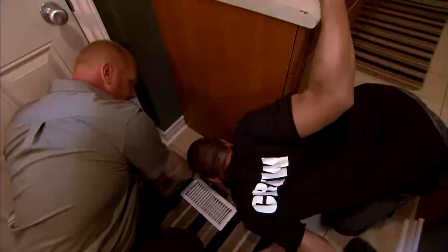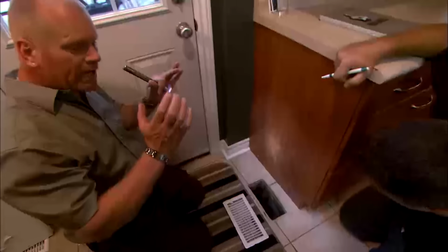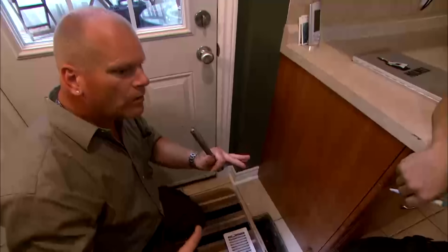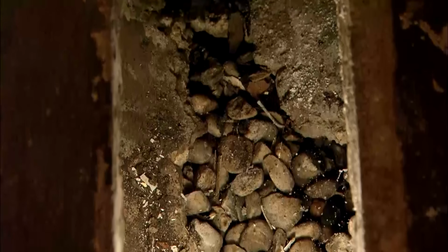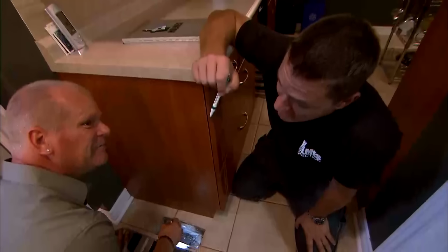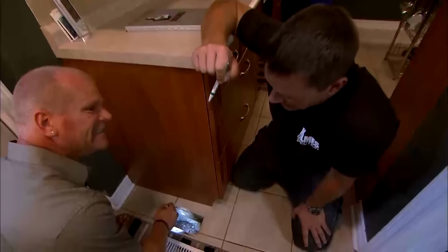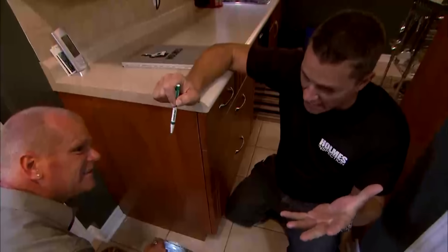Oh wow, they just cut it or bashed it apart right there. Now look at this way, now you see the 90, it's a galvanized 90. And where does that go to? It goes to this register in the bathroom right there. You're kidding me, so look at it. They run an actual sonotube line throughout, underneath all the concrete. Not to mention, I see water down there. Yeah, that's cardboard, it's gonna collect mold, mice, ants. Oh my God, and then you're gonna just spew all that into the air.